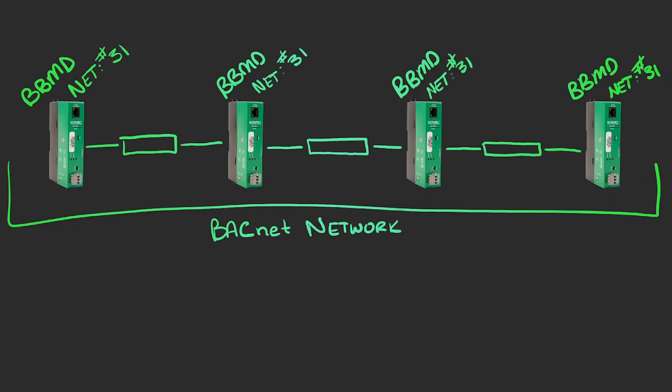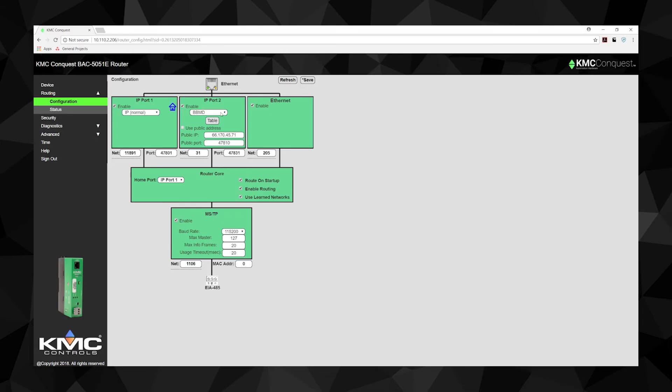Since BBMDs tunnel broadcast messages as unicast messages, they communicate point-to-point with other BBMDs. When configuring a BBMD, you must create a table of all the other router BBMDs you want to be aware of.